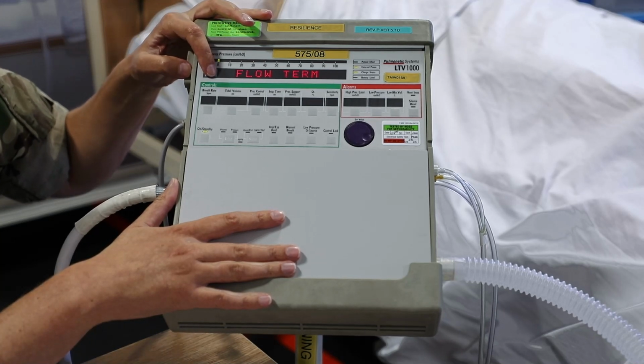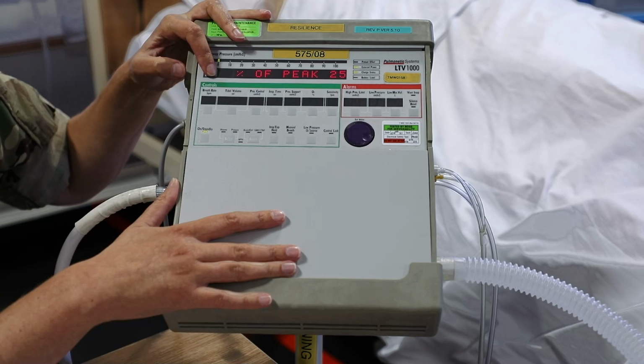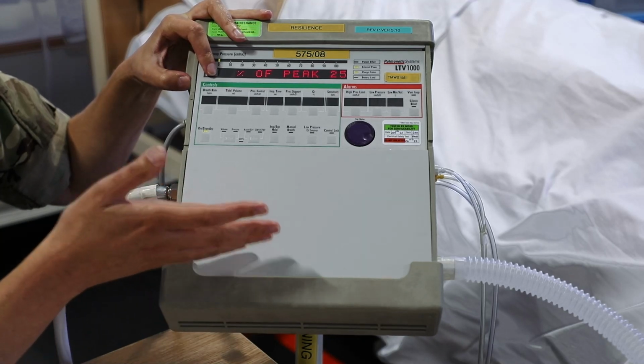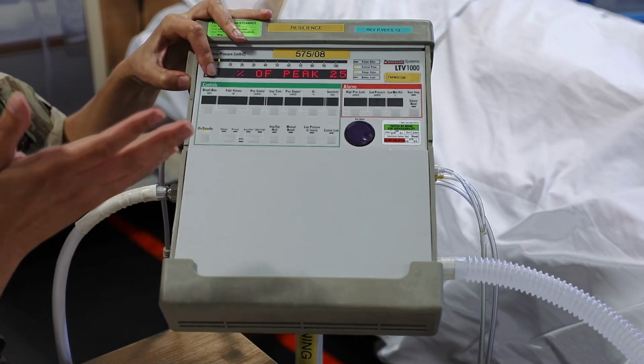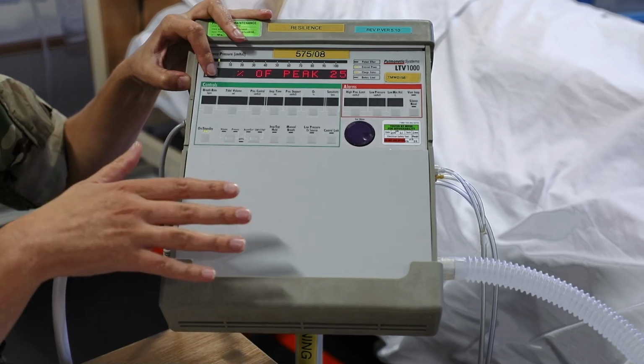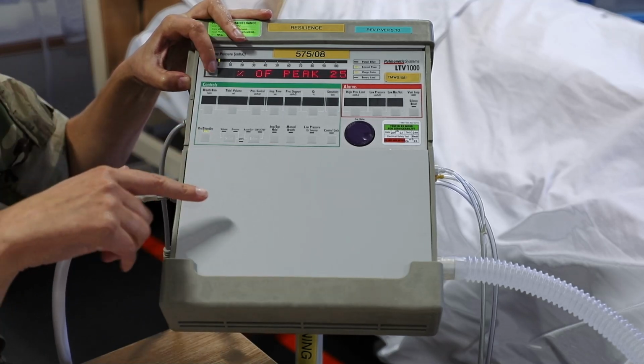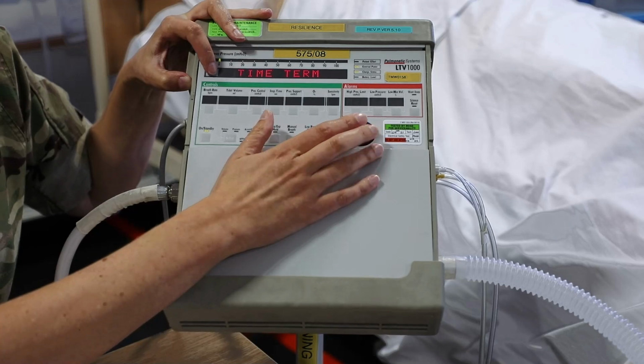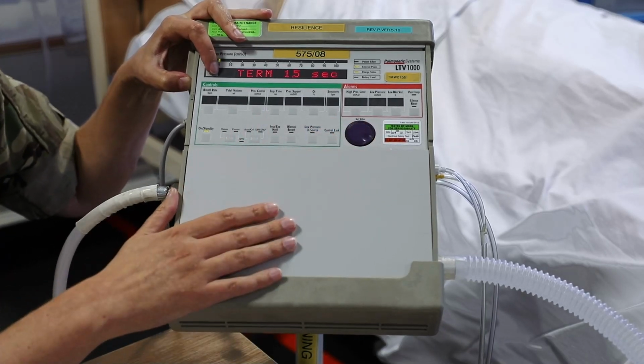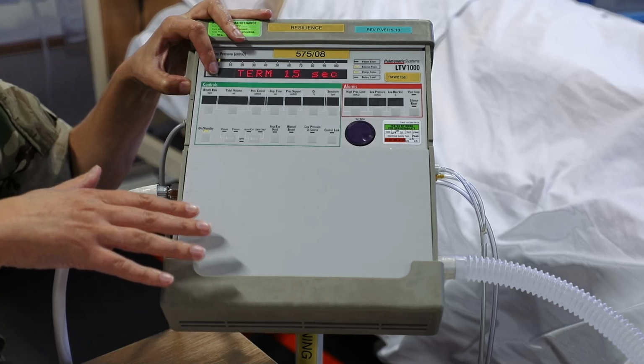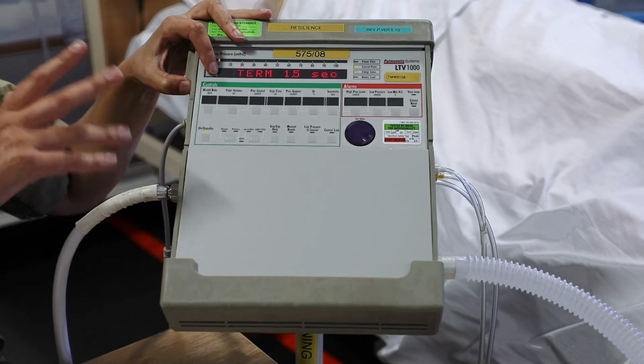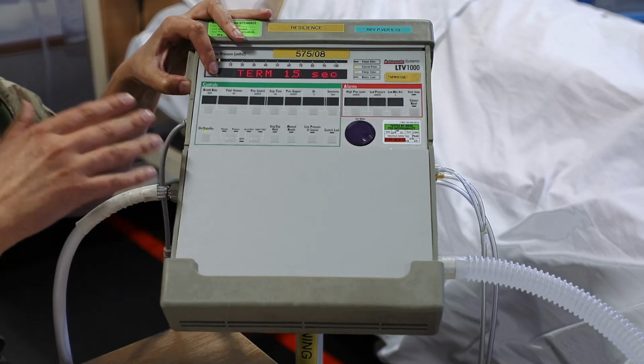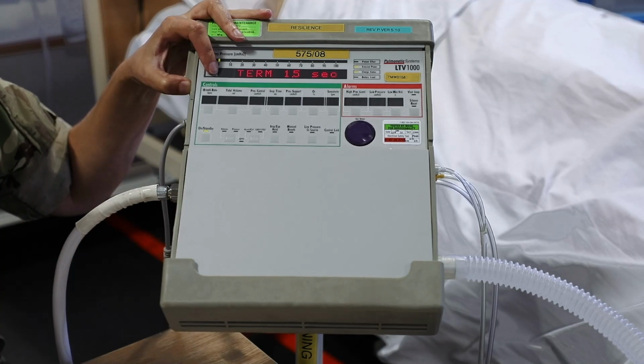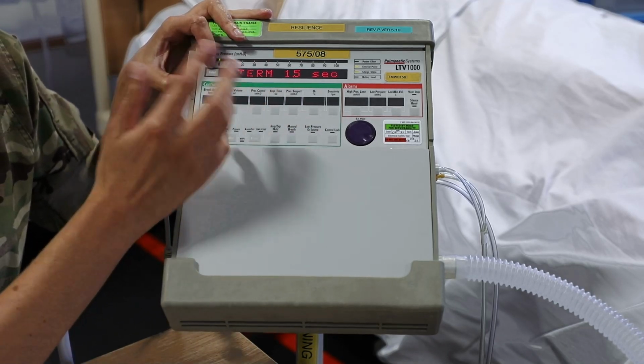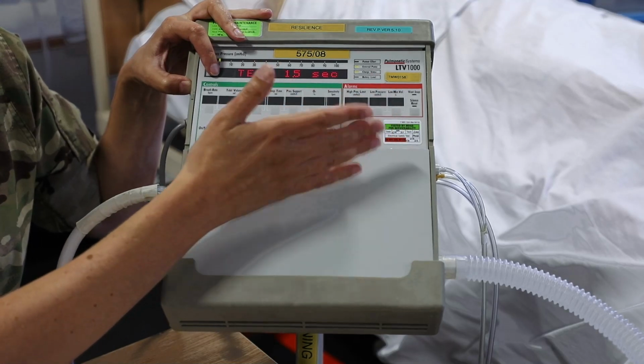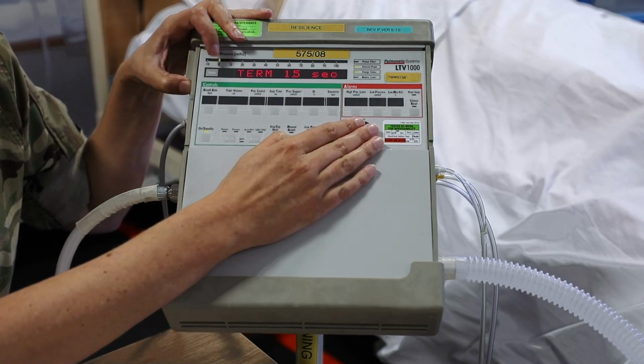And as standard, we have our flow termination set at 25% of peak. So if the inspiratory flow hits 25% of its peak flow, then it will cycle into expiration. And we also have our time termination, which will terminate a breath into expiration at 1.5 seconds. So you can adjust those two if you need to, but we tend to keep them as standard. And whichever one of those numbers hits first will terminate a spontaneous breath.